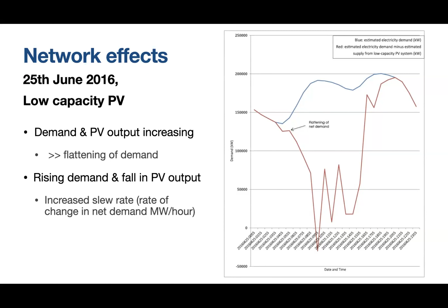I tend to think of this as two waves: we've got the demand wave, in blue, and the supply from the PV system. Combining those gives different effects. Where both demand and PV output are rising, we get a flattening of the net demand because one wave effectively cancels out the other. But where we have rising demand and falling output, what we've seen from this simplified model is an increase in what we call the slew rate, the rate of change in net demand, so that curve becomes steeper.